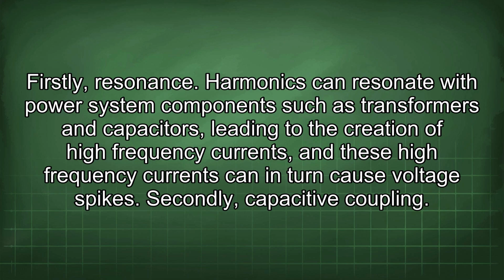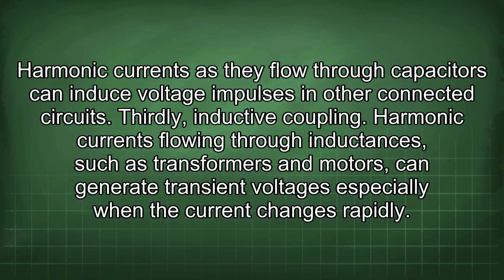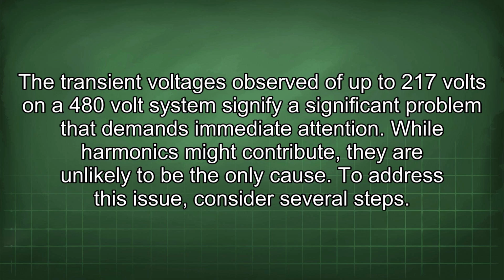Secondly, capacitive coupling. Harmonic currents as they flow through capacitors can induce voltage impulses in other connected circuits. Thirdly, inductive coupling. Harmonic currents flowing through inductances, such as transformers and motors, can generate transient voltages, especially when the current changes rapidly. The transient voltages observed of up to 217 volts on a 480 volt system signify a significant problem that demands immediate attention. While harmonics might contribute, they are unlikely to be the only cause.